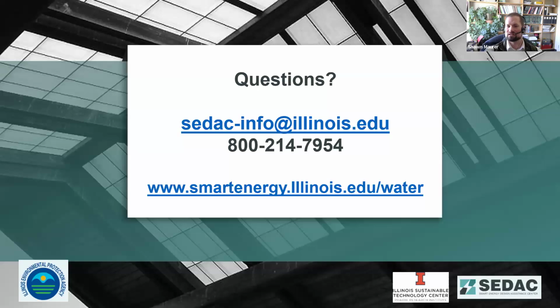Hey, one final question I had about SCADA processes. One of the things we've run across with some of the more advanced aeration systems, like ammonia-based controls, is calibration of those sensors and detecting that they're getting out of spec or need to be calibrated. Can SCADA systems be used to help automate and predict when that calibration needs to be done, to take some of that workload off operators, rather than just going out there on a regular time basis to ensure those things are calibrated?